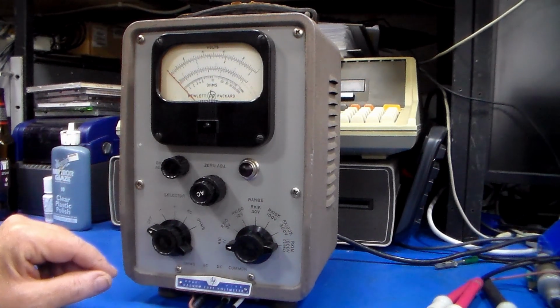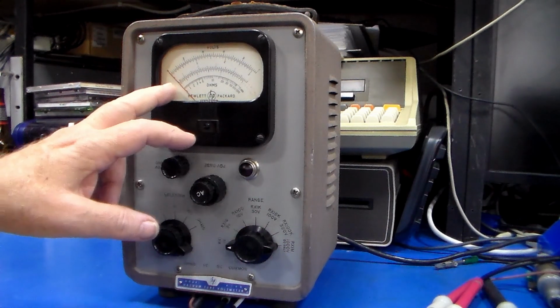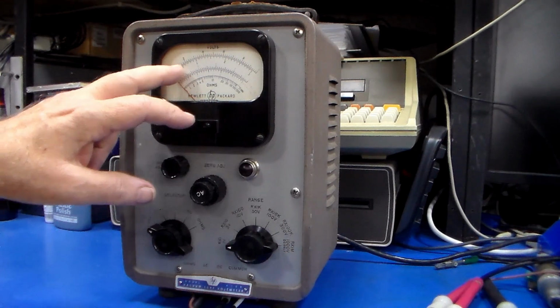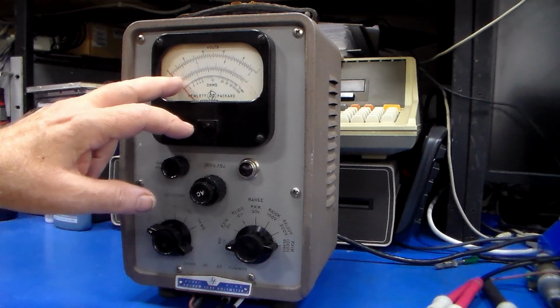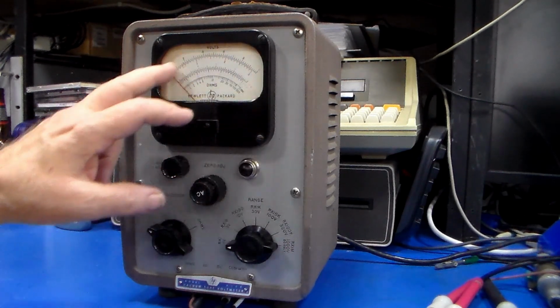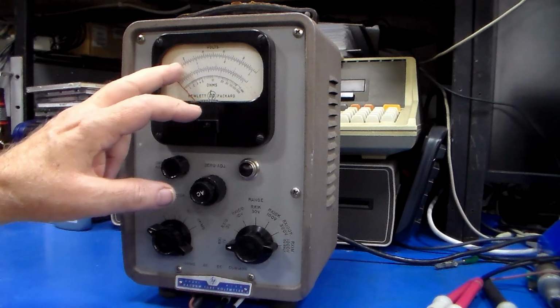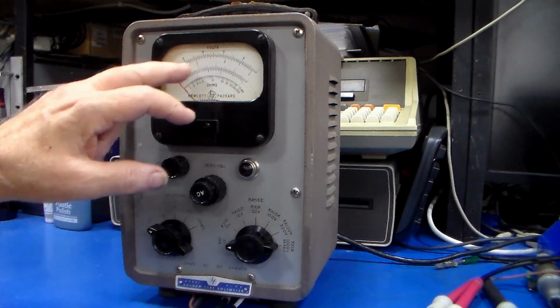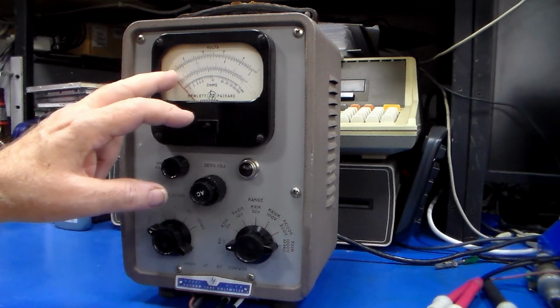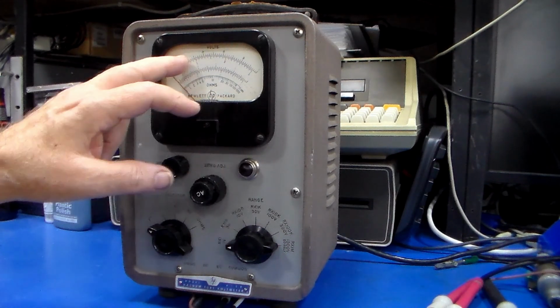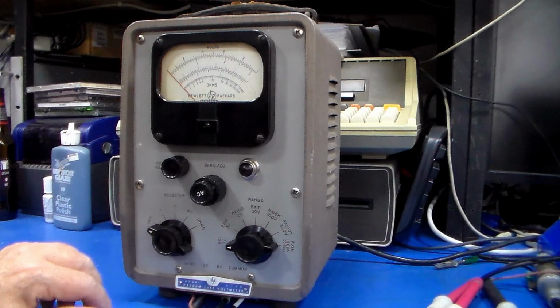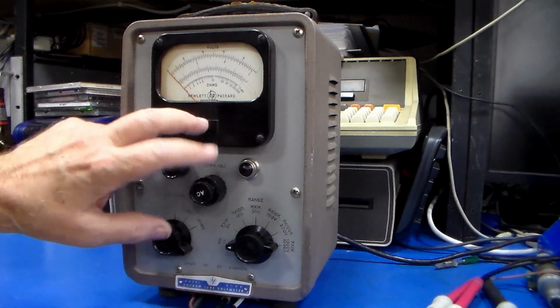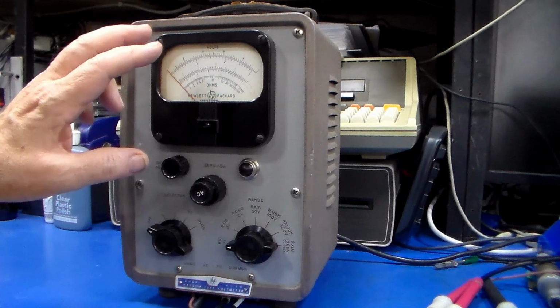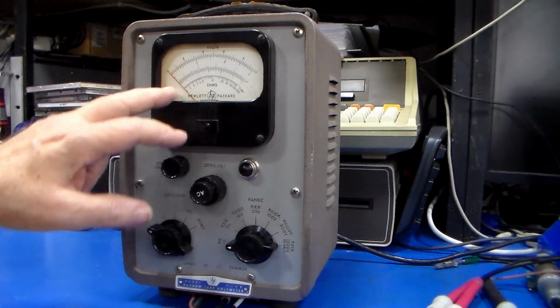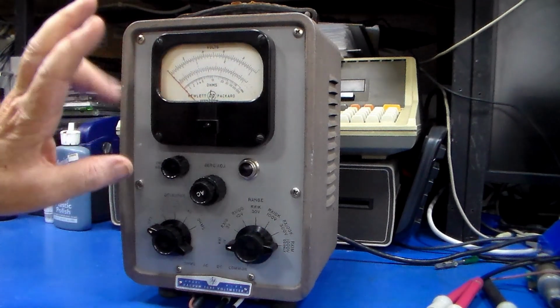Is there an issue with the meter movement? And after repeated tests that I performed, I was starting to find that occasionally the meter needle, particularly when you didn't have a lot of momentum, say going from full zero to full scale, but only going up the scale to say 20, 30, 40% or so, the meter would tend to look like it was sticking before it actually got to the setting that you had intended, and you could actually tap on the meter and it would then move a little bit, and similarly coming back to zero it was tending to stick, but it wasn't always in the same place.